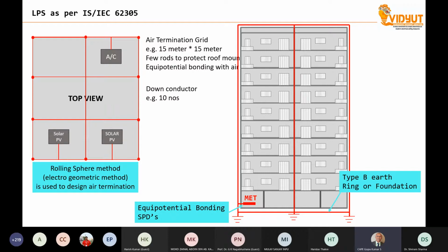Now, the first part of lightning protection is to create an air termination system. An air termination system is intended to intercept the lightning, in the sense that instead of hitting the building, the lightning is supposed to hit this particular air termination. There are two or three ways of designing the air termination. If you have a flat roof, what is recommended is a grid, say, for example, 15 meter by 15 meter.